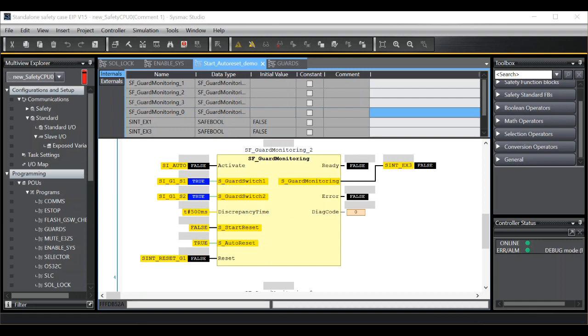Set up in this way, I would expect the output to stay false when the transition from false to true takes place on the activate signal. A manual reset will be required. However, once the function block is running, a transition on the guard from true to false to true will not require a manual reset.